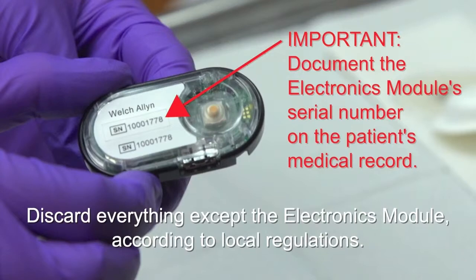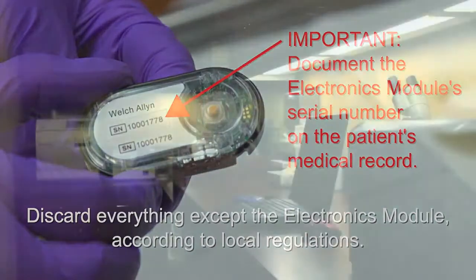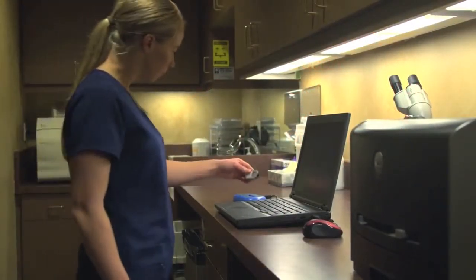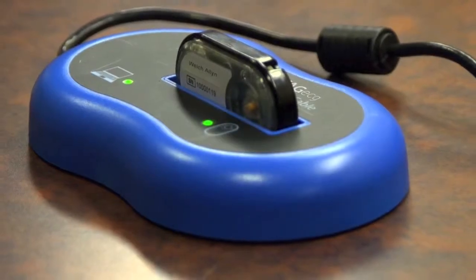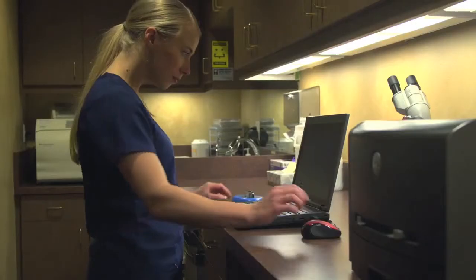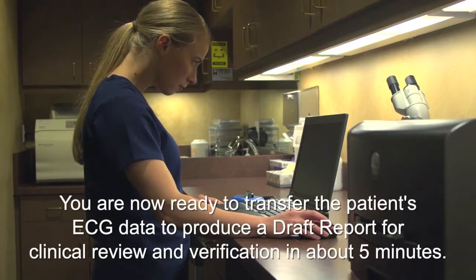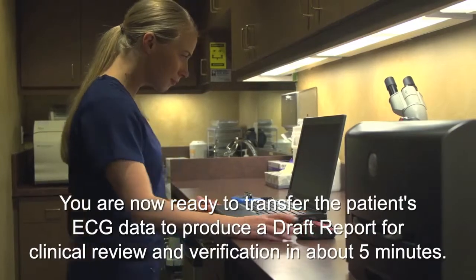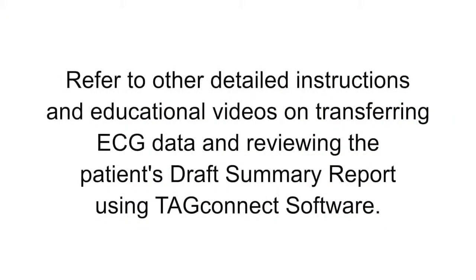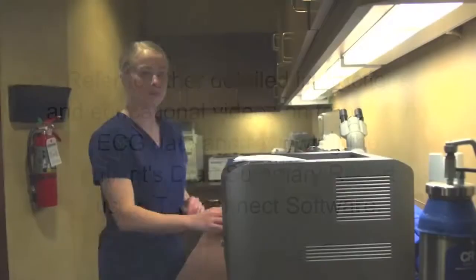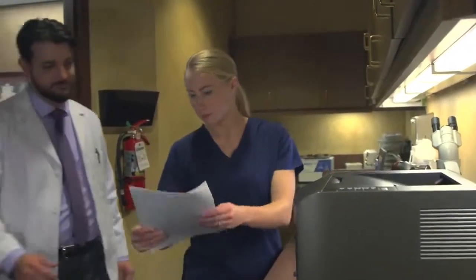Be sure to document the electronics module serial number on the patient's medical record for identification purposes. The electronics module contains the patient's complete ECG recording, up to 7 days. You are now ready to transfer the patient's ECG data to produce a draft report for clinical review and verification in about 5 minutes. Refer to other detailed instructions and educational videos on transferring ECG data and reviewing the patient's draft summary report using TAGconnect Software. This can be done conveniently and securely right in your clinical setting.